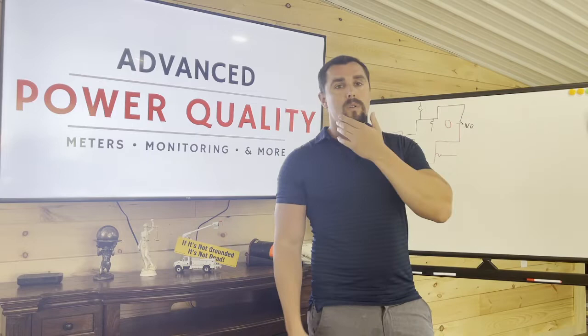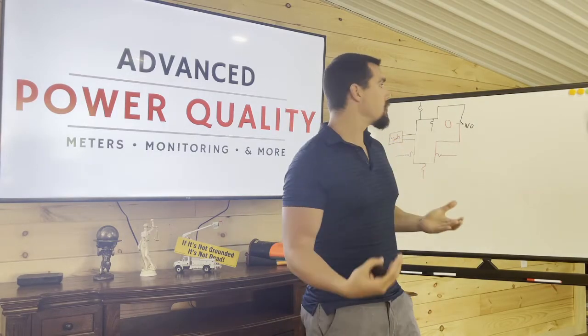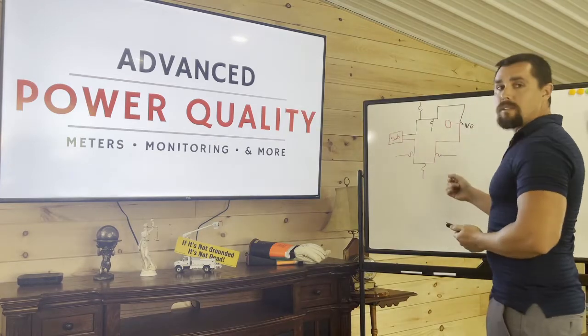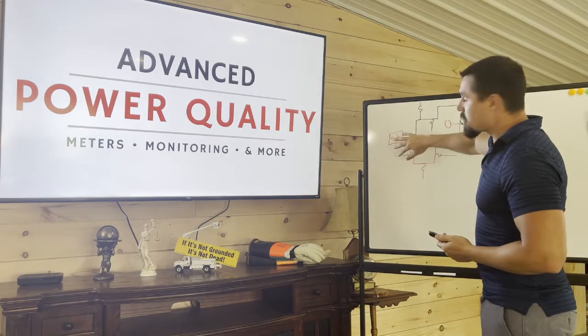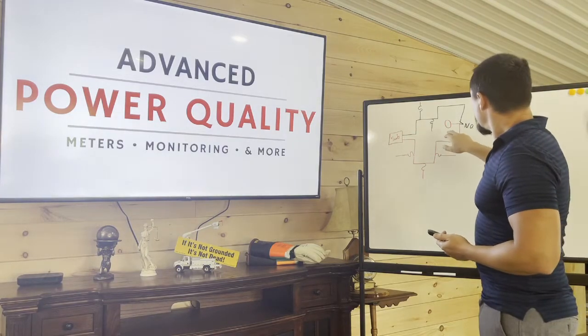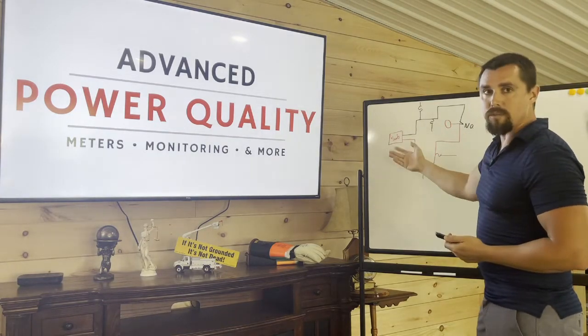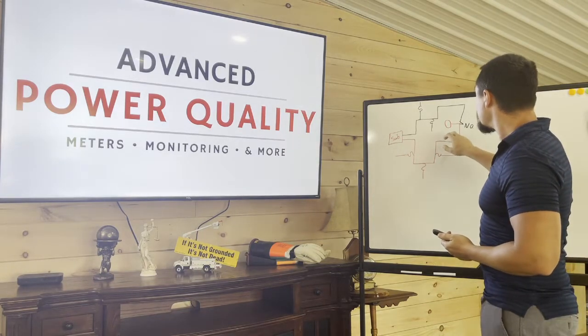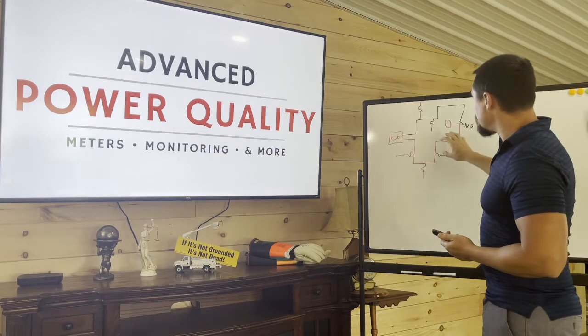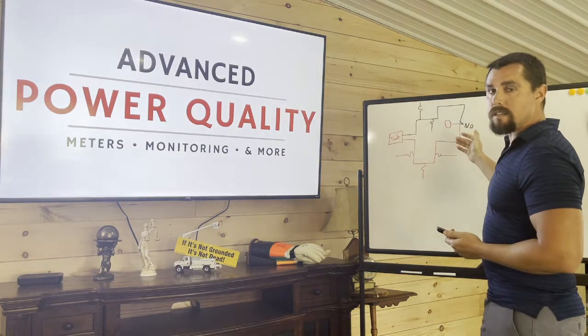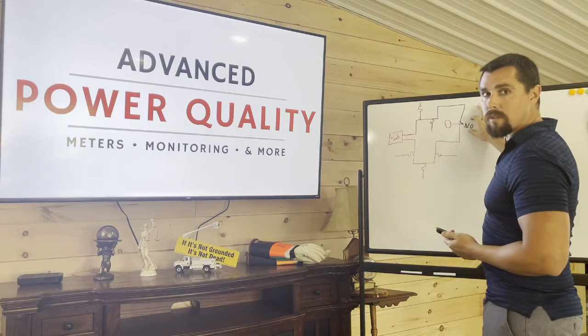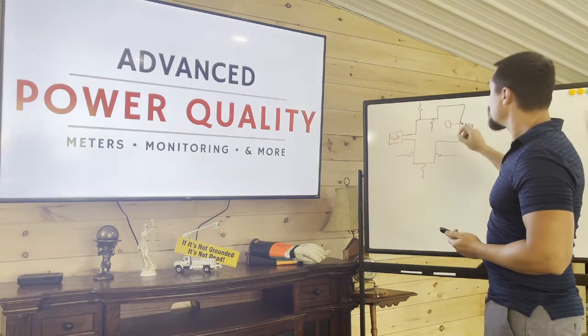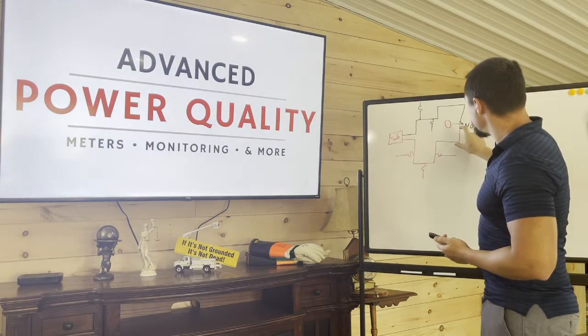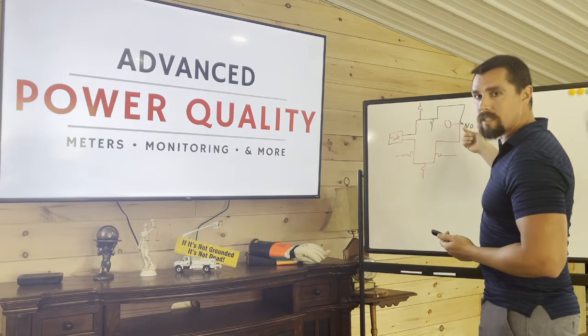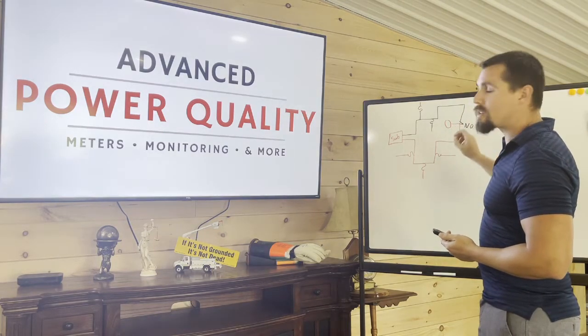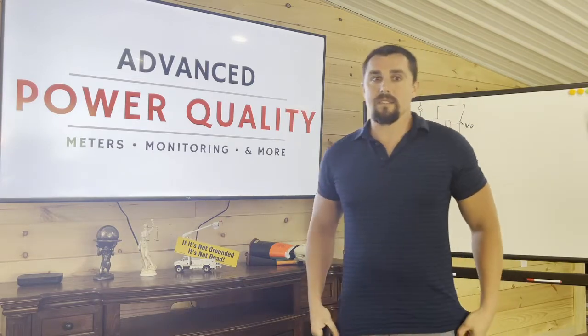And one other thing I want to discuss about ATSs. So what it is, you'll have the utility here, you'll have your substation. Out of the substation, you'll have multiple feeders. Say this is our customer. These are laterals coming off of the feeder. The customer's on one, but their preferred feed is our red feeder here. Their backup feed is the black feeder. And you have your normally open point here, typically identified by NO. So what happens is power goes out on the red feed, it switches to the black feed, but that's a 1 second delay. So like I said earlier, that's a long time for electrical equipment.